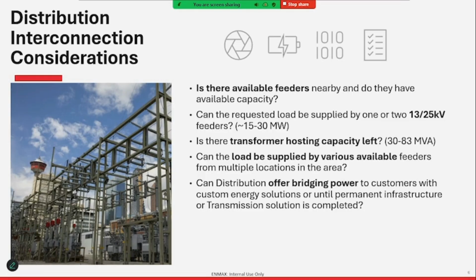Upstream transformers come in different sizes in our system, from 30 to about 83 MVA right now. So if you want to connect a 50 MVA data center load, does that limit based on location, or require using multiple transformers? And if there's bridging power or various feeders available, that adds complexity and can impact reliability at multiple sites, affecting the ability to transfer loads during adverse weather events, and adding potential stress points operationally.